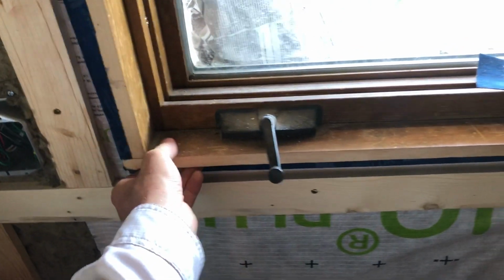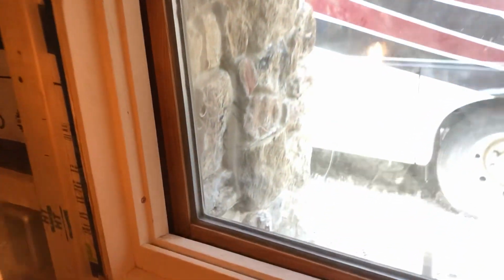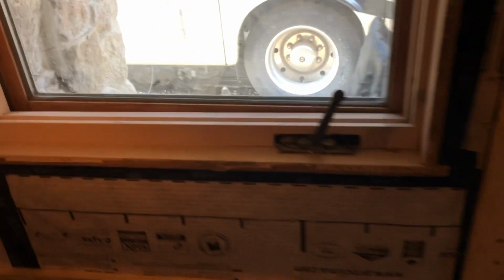So I know that there's little leaks like that supplying some amount of cubic foot per minute, but obviously not enough to register on the blower door. So I have a window over here that I've been operating just a little bit open to verify that the blower door is functioning properly and that the air leakage is just so low that it doesn't register.